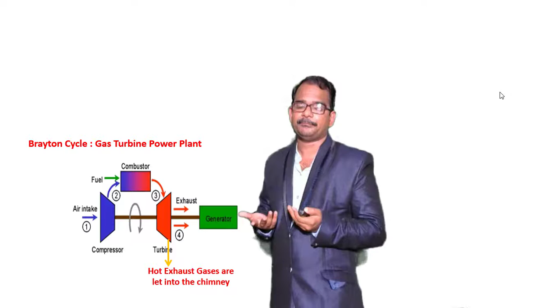So how could we utilize this heat? We have to utilize it by means of a device called a recuperator, which is a heat exchanger that transfers the heat from the exhaust stream of the gas turbine and sends it to the compressed air via the recuperator.